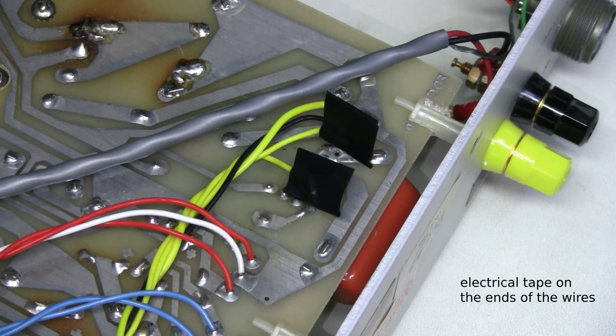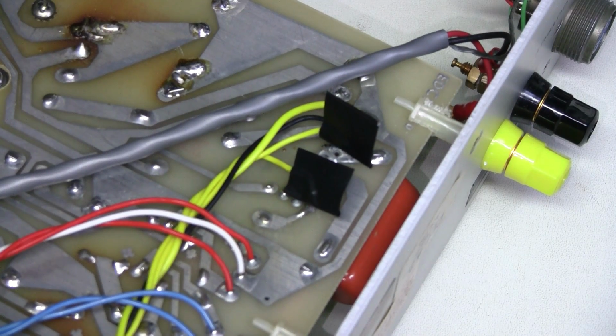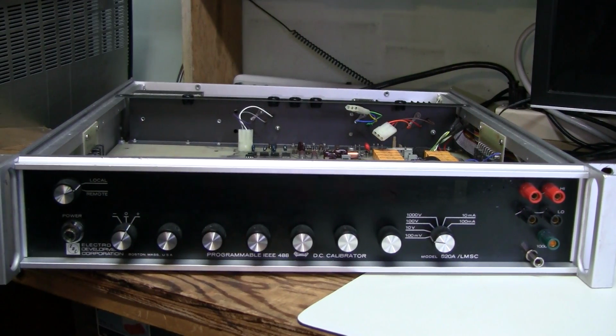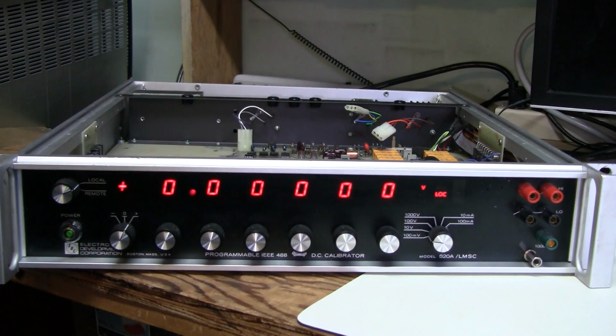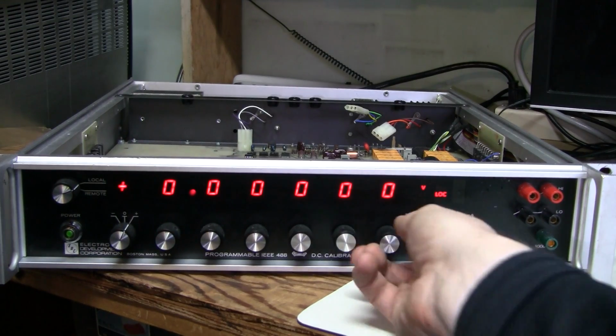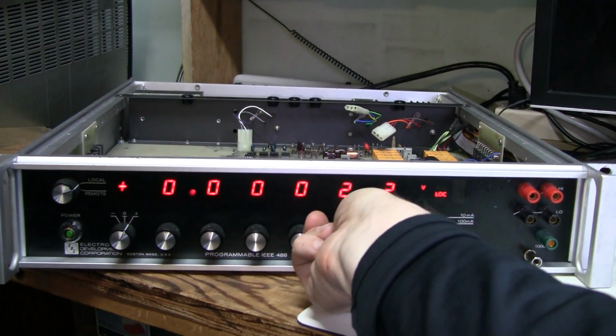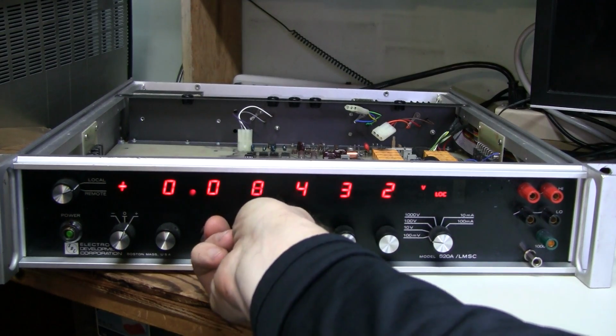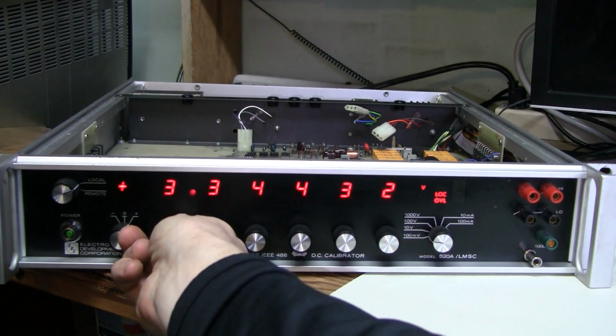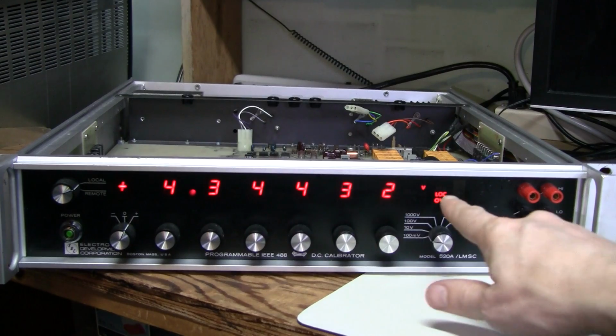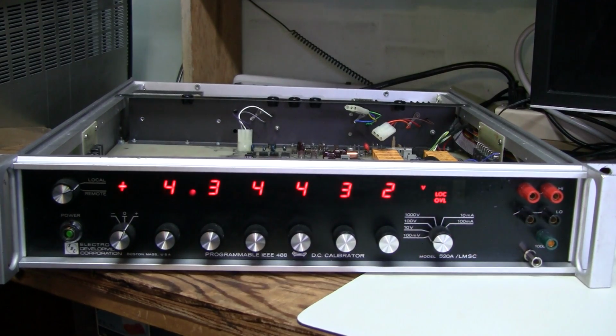I desoldered the wires from the transformer and installed a new fuse. Let's see what happens. Check this out. It's working. It shows this overload because there is detection that nothing is on the output, so it assumes that there is too much load.